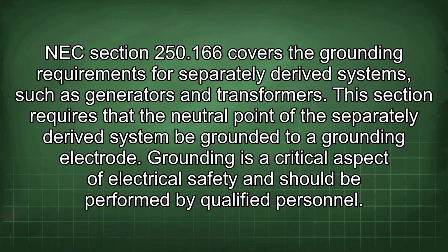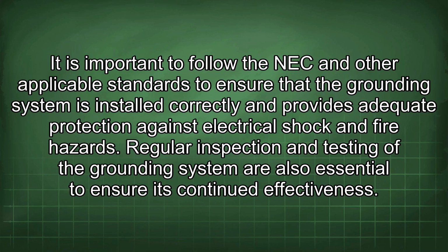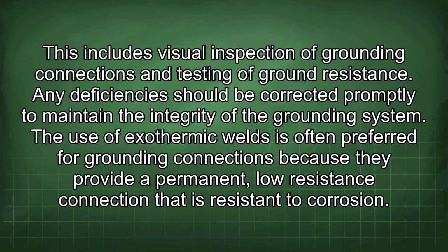Grounding is a critical aspect of electrical safety and should be performed by qualified personnel. It is important to follow the NEC and other applicable standards to ensure that the grounding system is installed correctly and provides adequate protection against electrical shock and fire hazards. Regular inspection and testing of the grounding system are also essential to ensure its continued effectiveness. This includes visual inspection of grounding connections and testing of ground resistance. Any deficiencies should be corrected promptly to maintain the integrity of the grounding system.